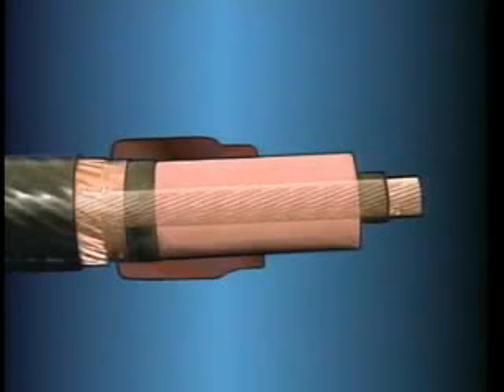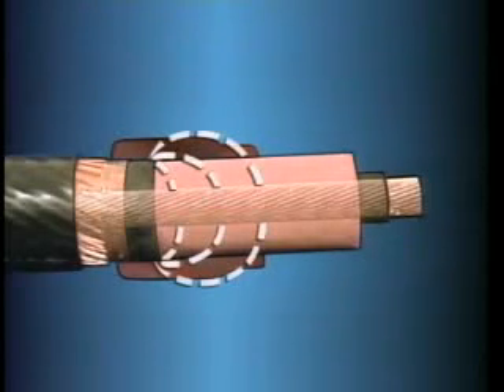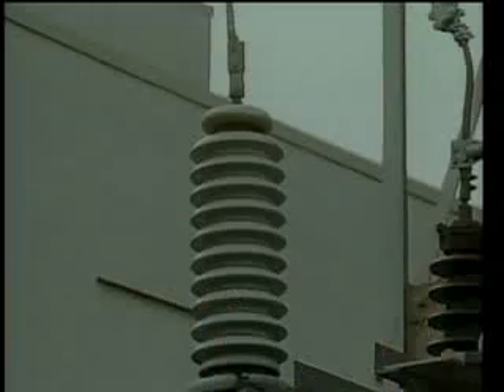At the termination, this higher K factor enables the capacitive material to concentrate the voltage stress in itself so that it doesn't concentrate at any given point in the insulation. So, voltage stress may be controlled at a termination by building a stress cone or by applying a highly capacitive material. Now, besides controlling voltage stress, a termination may also need tracking protection so that current doesn't track from the conductor terminal to the grounded insulation shield.